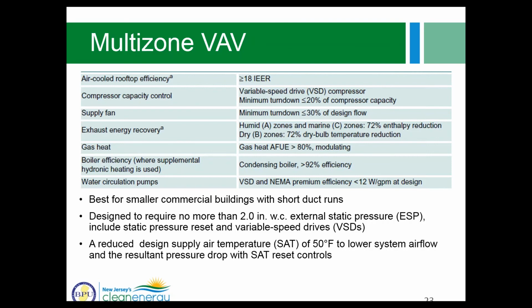You can have high performance multi-zone VAV system, and this system type is used in many cases in the modeled Appendix G baseline. Even though it's the same system type in the baseline, you can improve over baseline performance by having higher cooling efficiency, supply fan with minimum turn down of at least 30% of design flow, adding exhaust air energy recovery, using condensing boiler for heating, and using circulation pumps with variable speed drives, and consuming less than 12 watt per GPM at design conditions. So for reference, Appendix G baseline allowance is 19 watt per GPM.